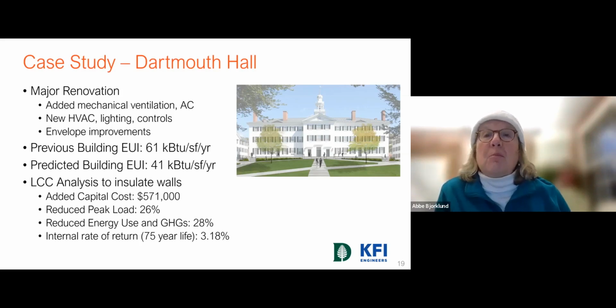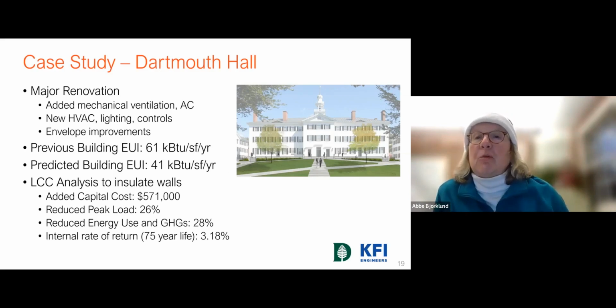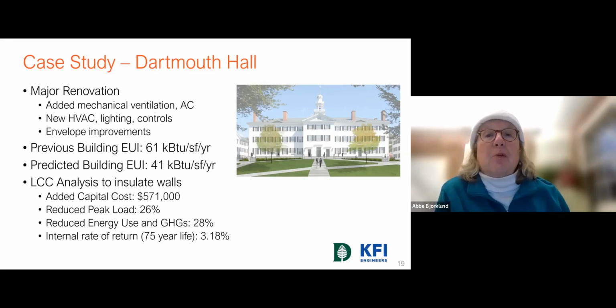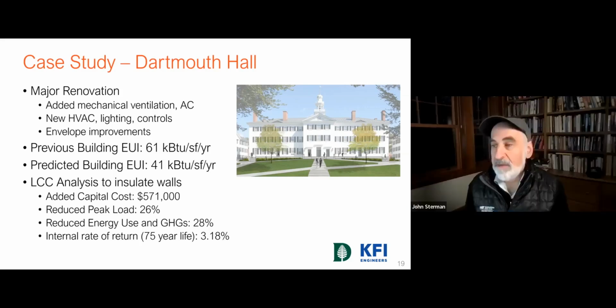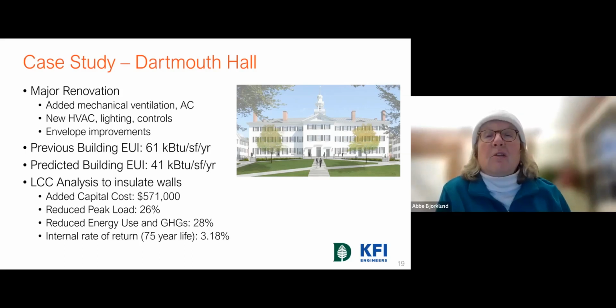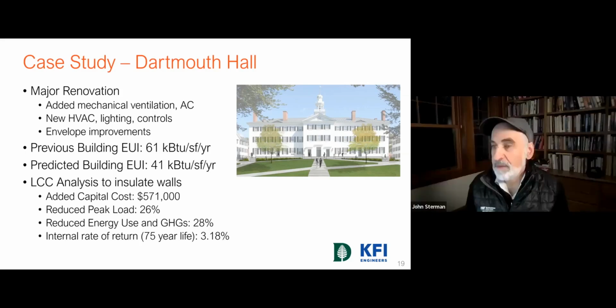We're trying to minimize the amount of air and limit it really just to the ventilation. Where we have to provide supplementary heating or cooling beyond what we're getting from the air system, we're providing that with water systems. The heat recovery on the DOAS system—is it just sensible, or also energy recovery? No, it's a heat wheel. It's sensible and latent.